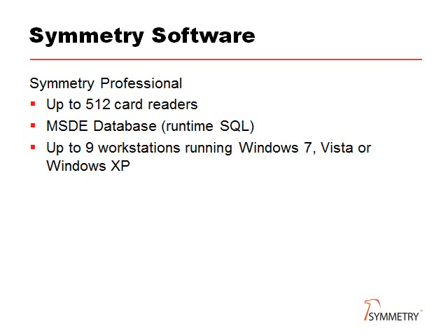Symmetry Professional software can support up to 512 readers, and all configuration information, event logs, etc. are stored in an MSDE database. Symmetry Professional is usually a single PC solution, but it is possible to support up to 9 workstations using a variety of Windows operating systems.